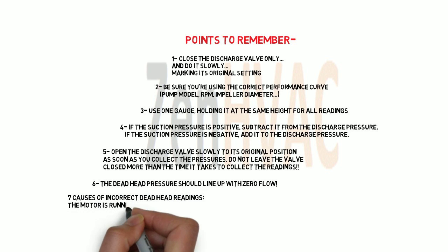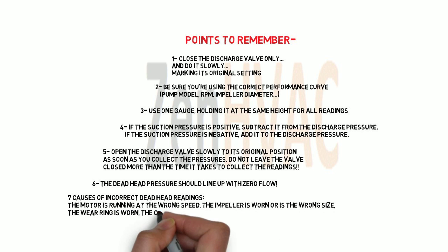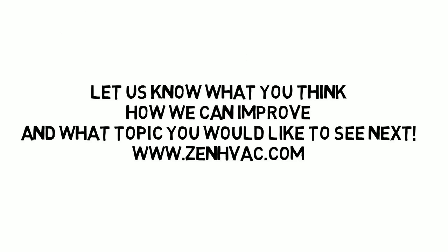Seven, causes of incorrect readings would be the motor not running up to speed, the impeller is worn or it's the wrong size, the wear ring is worn, or the cut water is compromised. Let us know what you think, let us know how we can improve, and more importantly, let us know what you'd like to see next. Thank you for watching.